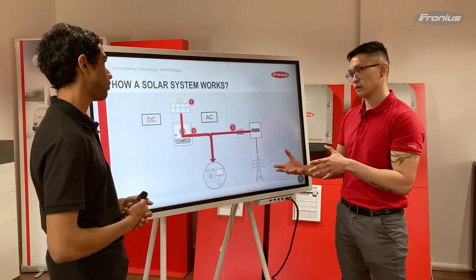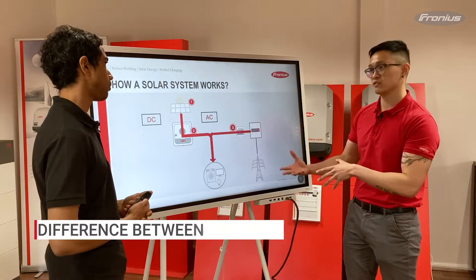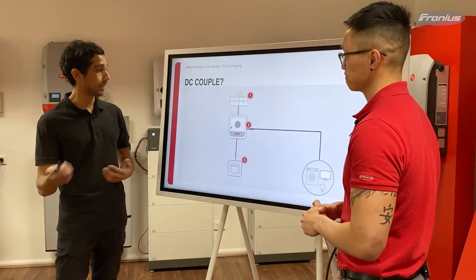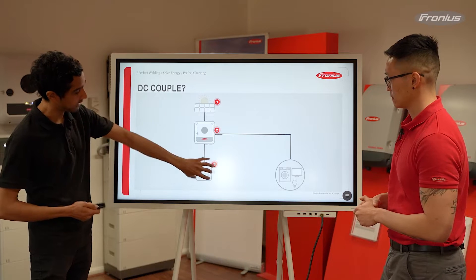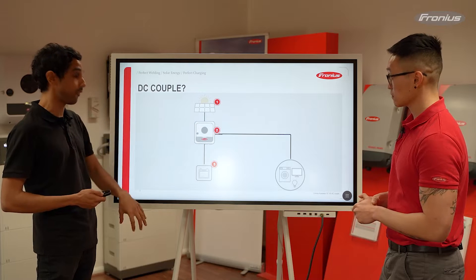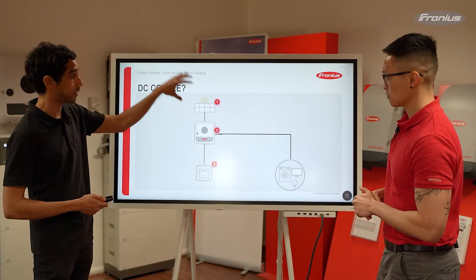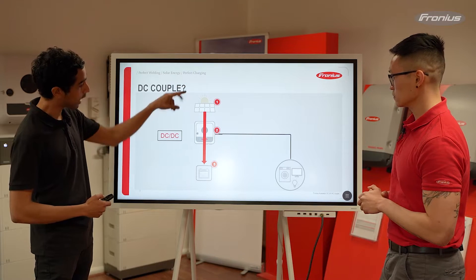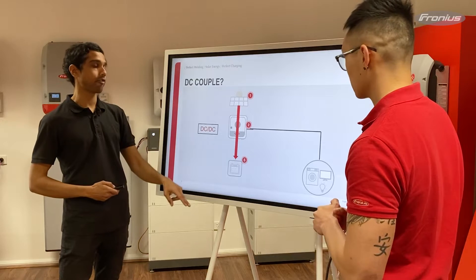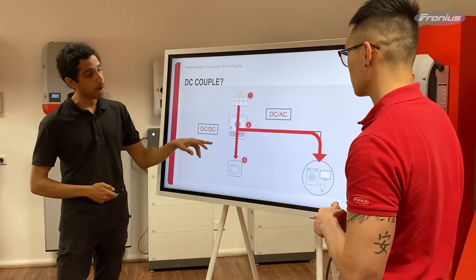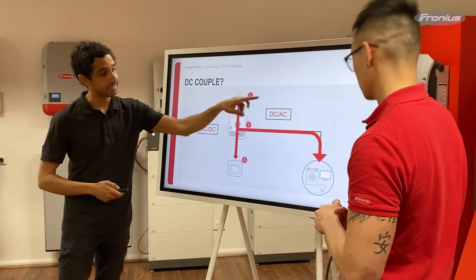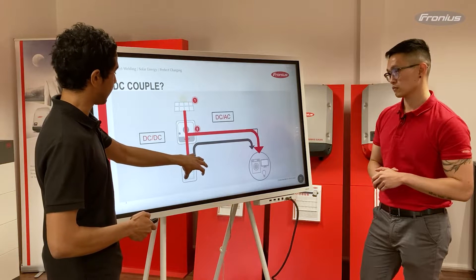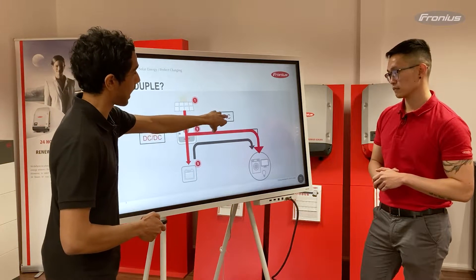So this is basically how a solar system works. A lot of installers ask us what's the difference between a DC and AC coupled solution. Starting off with the DC coupled solution, you've got a DC coupled battery now attached directly to the inverter. A DC coupled battery can accept DC power, so there's no conversion required — it comes through as DC power and goes into the battery to charge it. When you want to send power to your loads, the inverter converts the DC power into AC power, whether that's coming from the panels or from the battery.